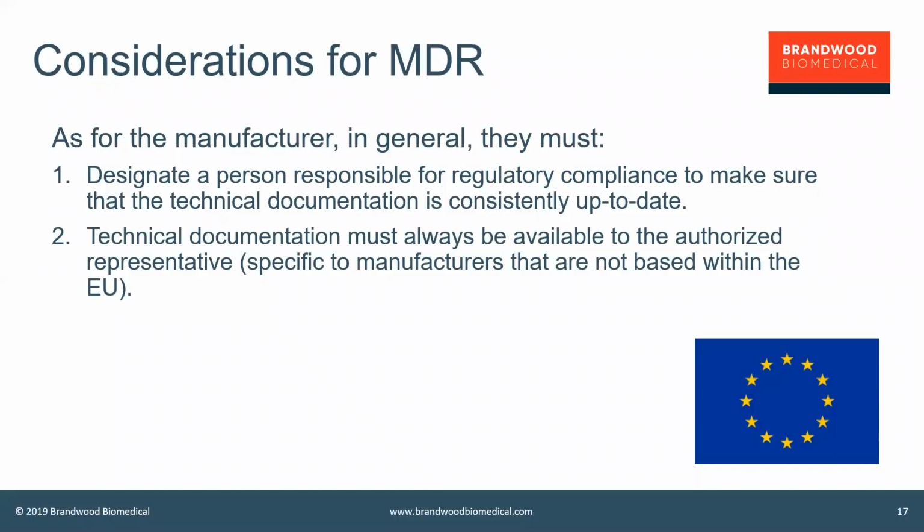We've really been in a situation where the authorized rep is really there to help with post-market activities and to address complaints and to make sure that those are triaged per the European requirements. Now, there is an expectation that that documentation will lie with the authorized rep so that if a notified body wants to review that because they've gotten a complaint or they've seen trending, that they can look at your documentation to either suggest that you need to do additional activities or to kind of dismiss it for your specific product. That needs to be readily available. Okay.